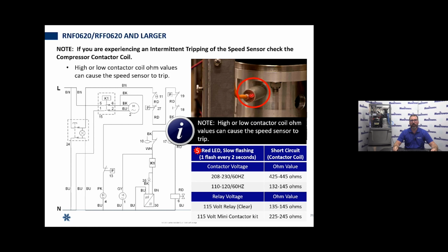So a slow flashing, once every 2 seconds, red LED means that we have an issue with the current through the motor contactor coil circuit. As you can see in the wiring diagram, it's wired in series with the motor contactor coil. So it's basically looking for an overcurrent condition at all times. Another safety feature that's built into that rotation sensor.